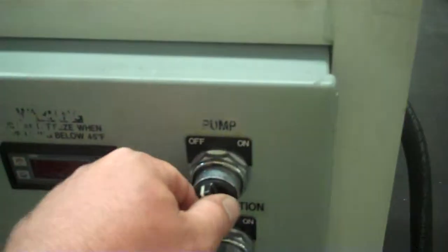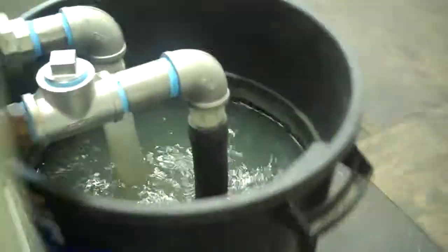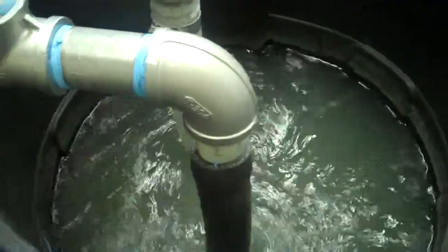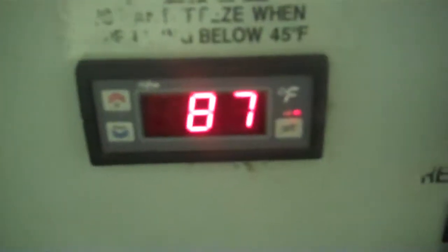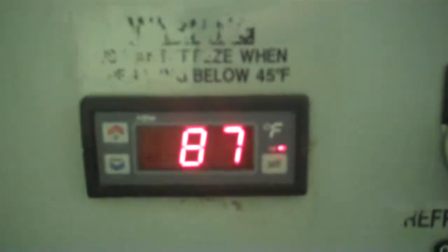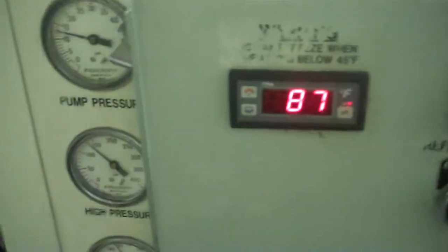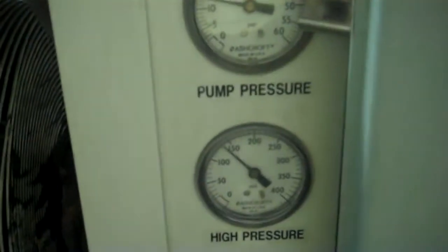We're going to go ahead and start by powering up by simply turning the pump button on. When you do that, you see we got some flow in our little test tank there. The controller is telling us we're at 87 degrees right now. And all our gauges work. Got our pump pressure, our high refrigerant pressure, and our low refrigerant pressure.